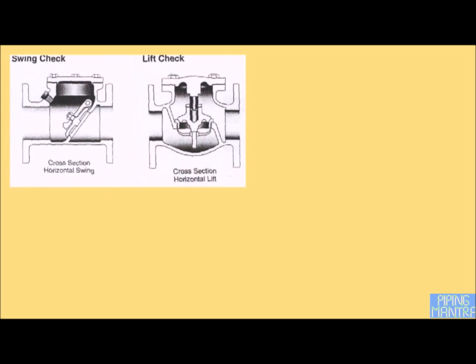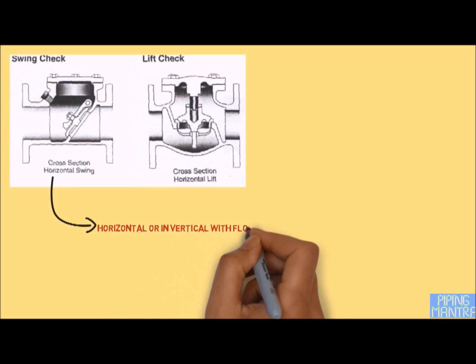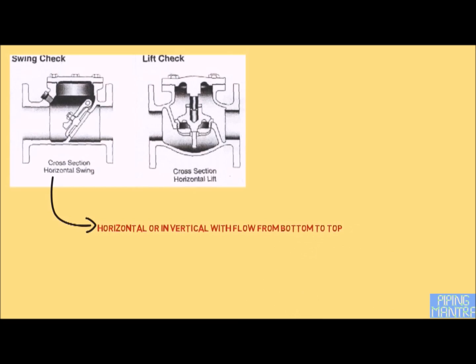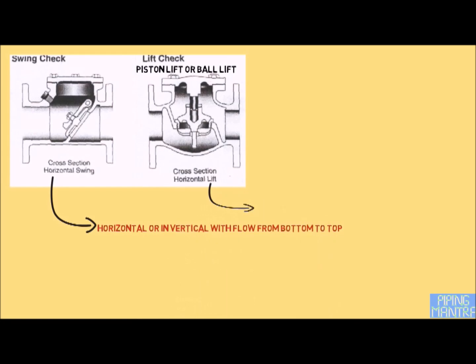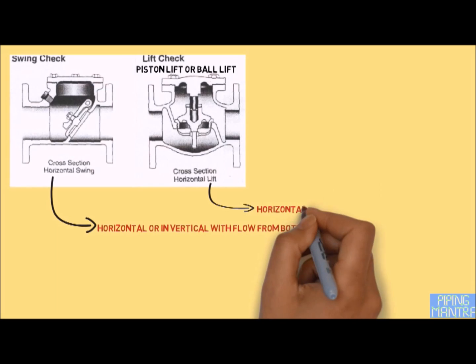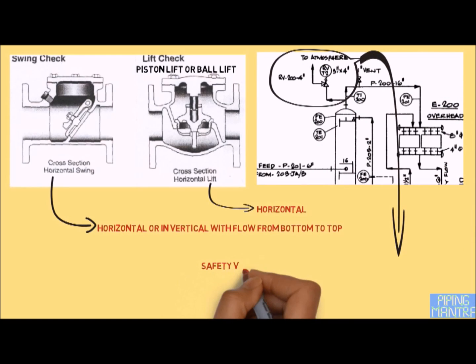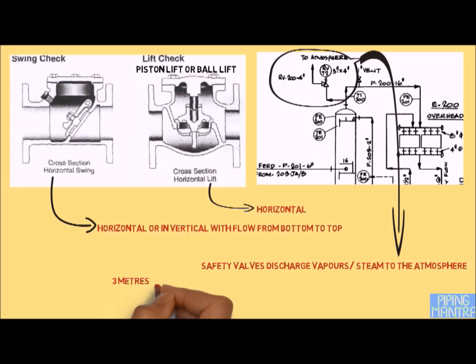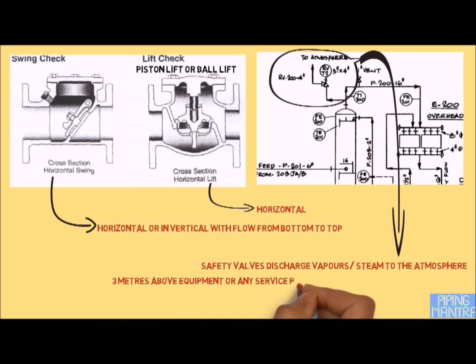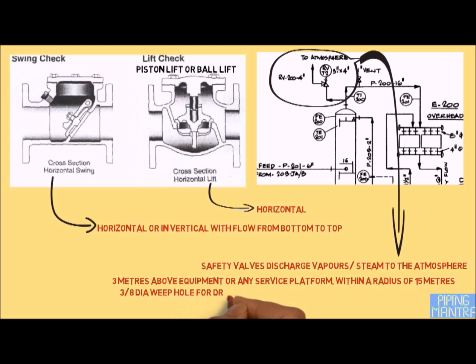For non-return valves (NRVs), the first type is the swing check valve, which can be placed vertically if the flow is from bottom to top. The second type is the lift check valve — piston or ball type — which must be placed horizontally and should not be installed vertically. For safety valves, when discharging vapor or steam to atmosphere, the outlet pipe should terminate at 3 meters above the equipment or any service platform where personnel movement is present, and within a radius of 15 meters of the valve. A 3/8 inch diameter weep hole is required for drainage at the low point of the line.